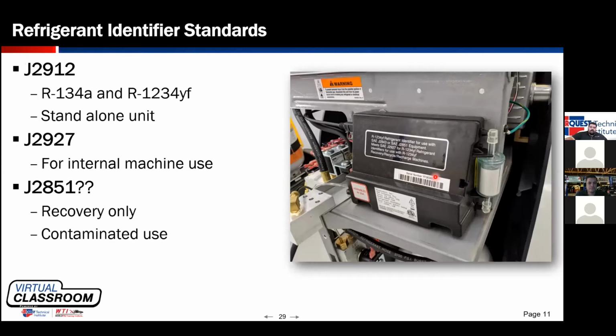Now, one thing to note on the identifiers for the R machines, you don't see this a whole lot because it's under the cover on a lot of the machines, but just like a handheld standalone identifier, we have a filter. This filter periodically needs to be changed. When the outside of the filter element starts to turn colors, that means that it has been exposed to moisture or oil and it needs to be replaced. That filter is a line of defense on your refrigerant identifier.